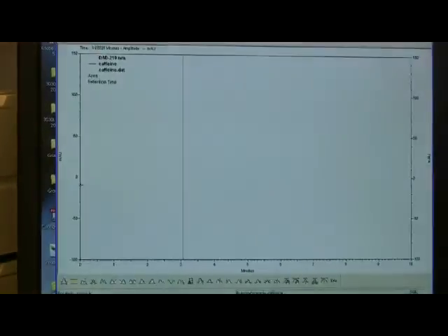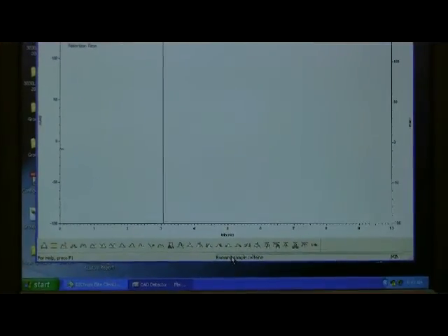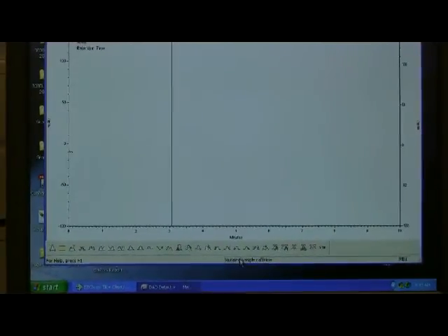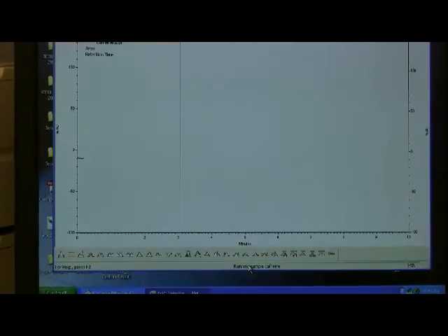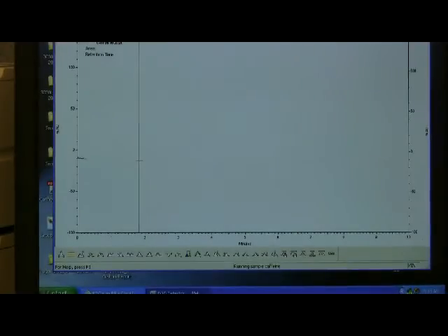As you can see now, it says running sample, whereas before it was waiting for trigger. And here is our UV trace. So it's very important that they do those steps in sequence, else they might screw up the starting of the instrument.